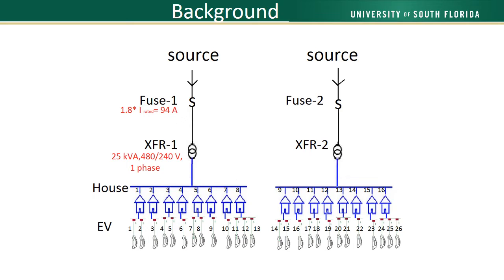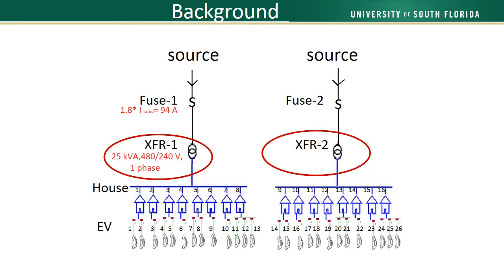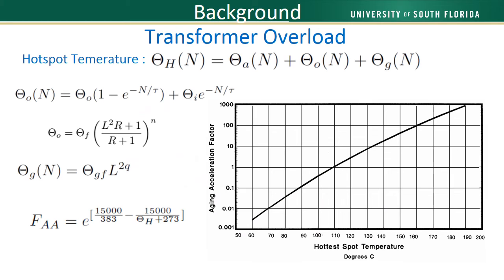Transformers are the principal component in electricity distribution. The customer transformer faces the most impact of EV inclusion, hence the focus of our research. Typically, these transformers, except for 1 and 2 in the figure, are smaller in capacity, ranging between 10 to 100 kVA, and are fuse protected. Because of the convenience and low cost, most EV drivers do more than 80% of their charging at home. So if the households under a particular transformer adopt EVs aggressively, the transformer will be overloaded soon and require replacement. The hotspot temperature of a transformer is a sufficient parameter for aging estimation.